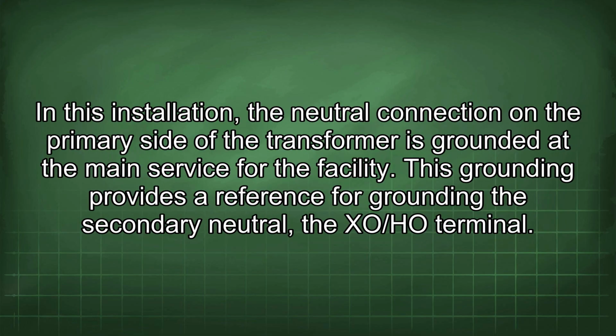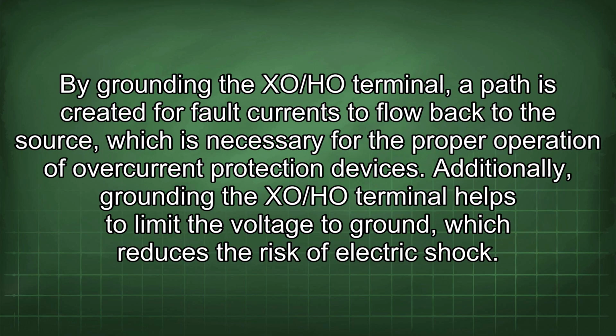In this installation, the neutral connection on the primary side of the transformer is grounded at the main service for the facility. This grounding provides a reference for grounding the secondary neutral, the XO/HO terminal. By grounding the XO/HO terminal, a path is created for fault currents to flow back to the source, which is necessary for the proper operation of overcurrent protection devices. Additionally, grounding the XO/HO terminal helps to limit the voltage to ground, which reduces the risk of electric shock.